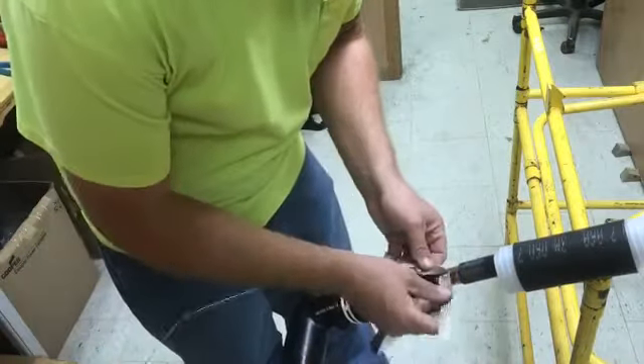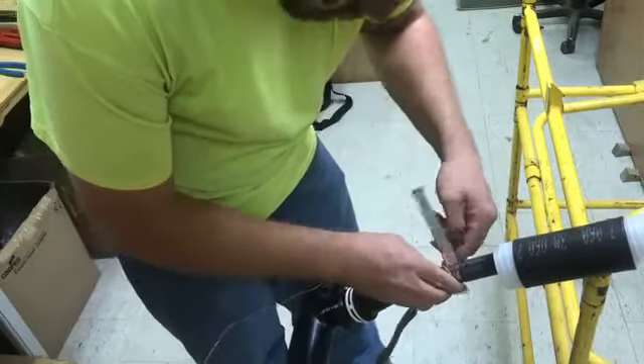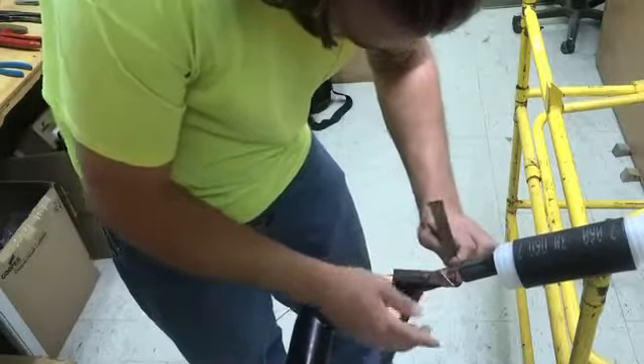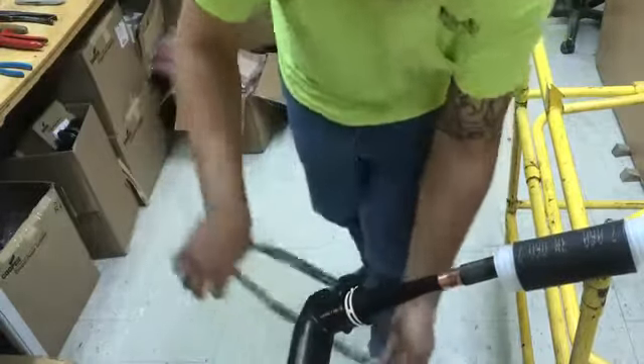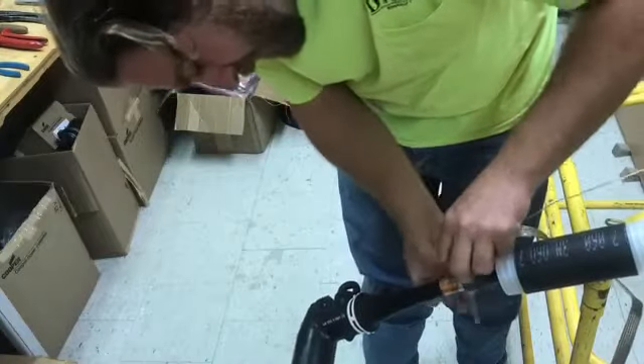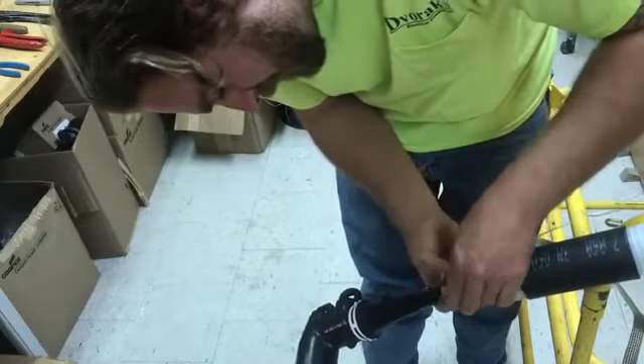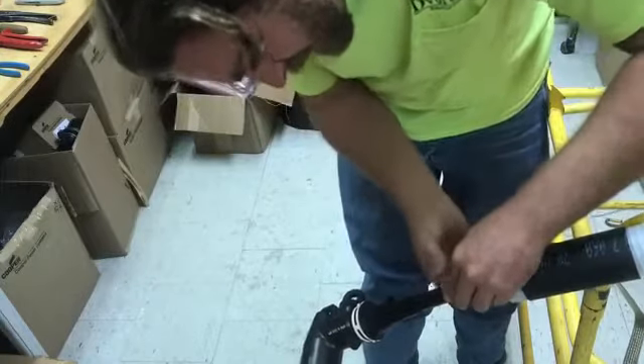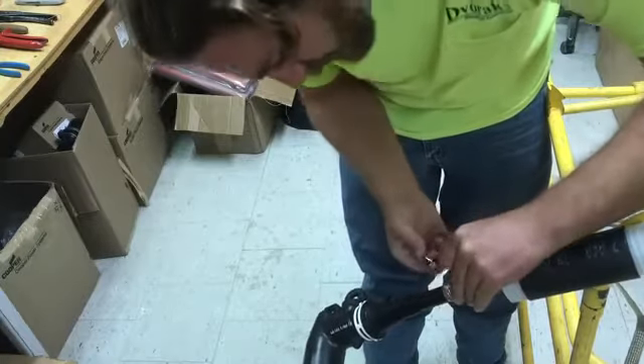Align the supplied ground braid in the SA2 kit onto the cable, mark and cut as to not let the ground braid overlap. Install the ground braid directly onto the ground tape shield. Ensure that the ground braid does not overlap and secure with a constant force spring and a wrap of copper tape.